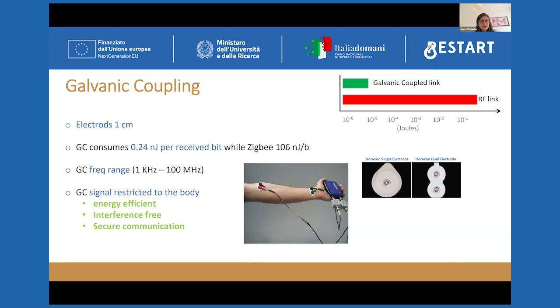And as you see here, the energy consumed by galvanic coupling is much lower than, for example, ZigBee, which is one of the standards of radio frequency. And this is the frequency range, which usually goes from 1 kHz to 100 MHz. The main feature of the galvanic coupling technology is that, since there are currents, the signal is restricted inside the body, hence it is interference-free and secure because there is no propagation outside.